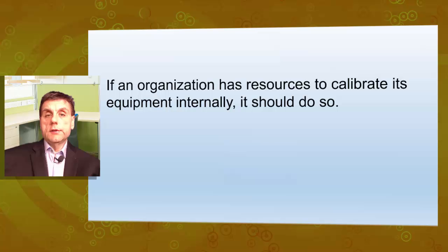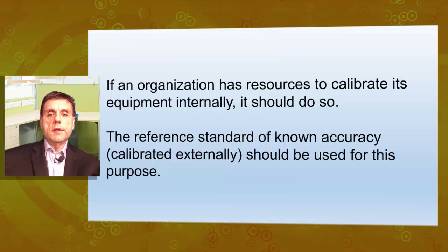If an organization has resources to calibrate its equipment internally, it should do so, because the most common reason is, first of all, to be in charge of its own process and to save the costs. The reference standard of known accuracy, calibrated externally, should be used for this purpose as a main standard for internal calibration.